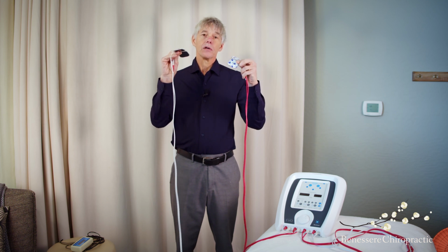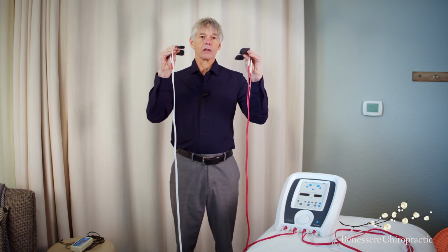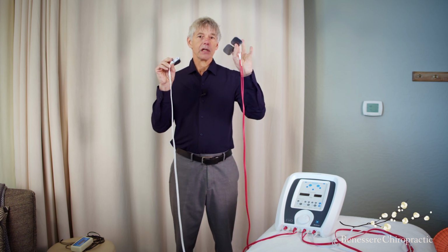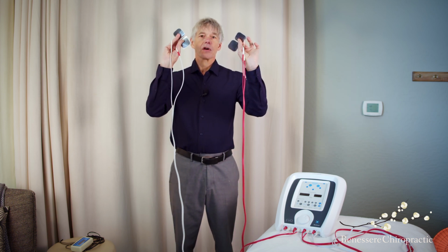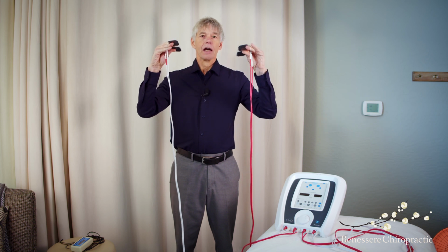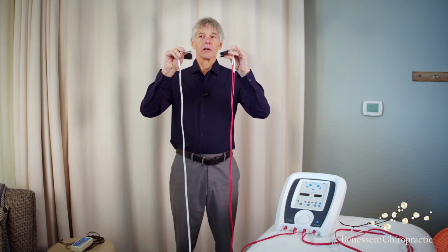With the interferential current, we are utilizing a current that flows between these two pads and a current that flows between these two pads. As the current is flowing between the pads, they are creating an intersection in the center. As the currents interfere with each other, they drive the current deep into the tissues, thus interferential, having an interference in the current, and we're able to have a therapeutic effect on the deeper structures within the tissues that we're wanting to work on.